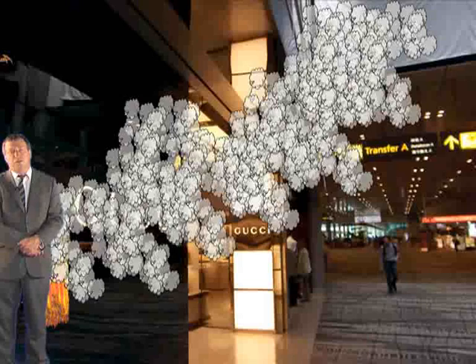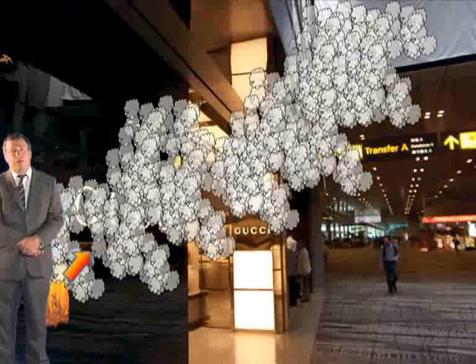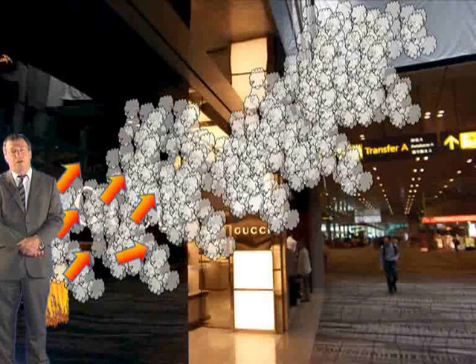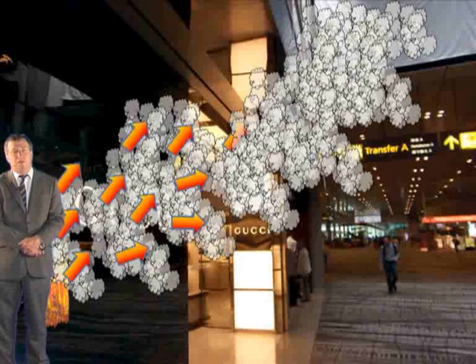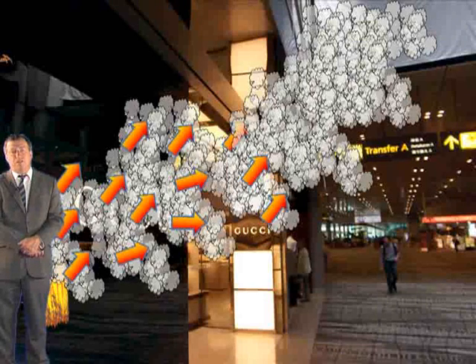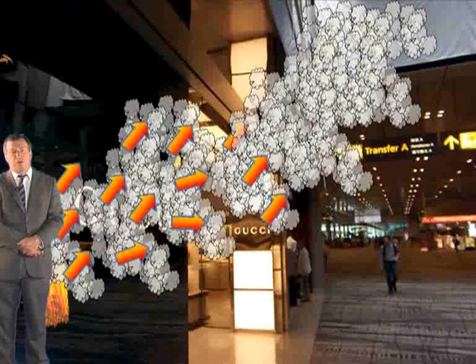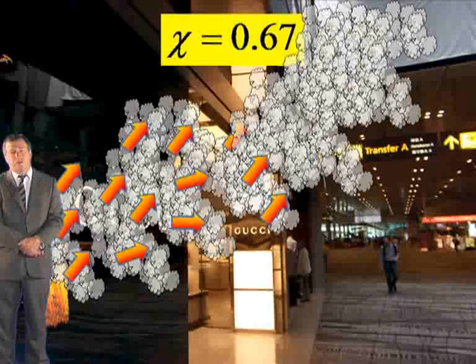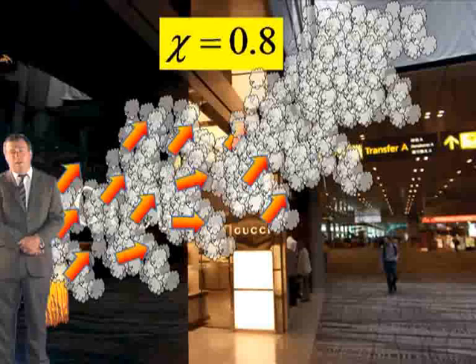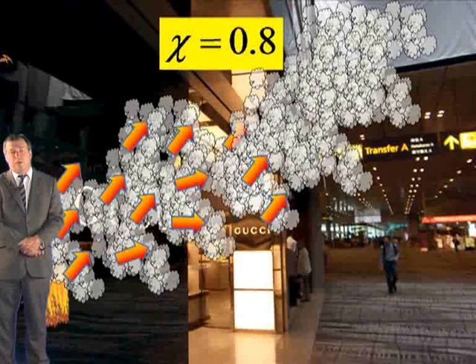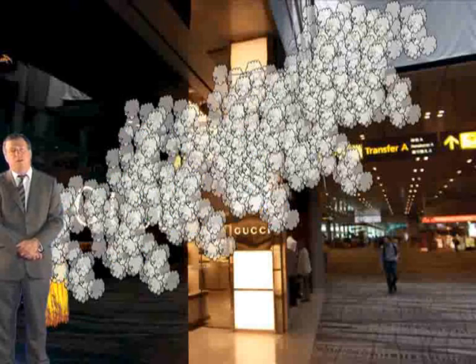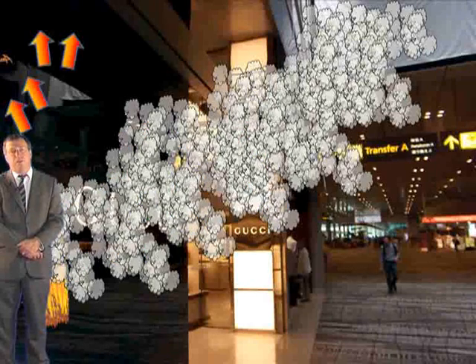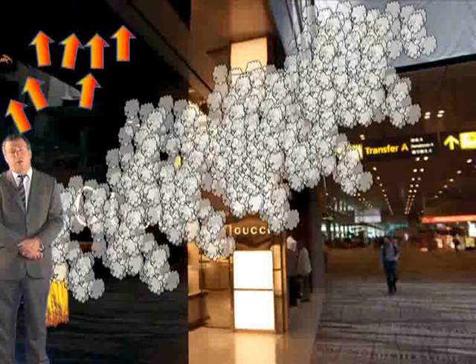BS 7346 Part 4 gives a discussion about the amount of heat that might be carried in the smoke as it leaves the room of fire origin. If you recall, for axisymmetric fires, we assumed a value of chi of between 0.67 and 0.8. This was the fraction of the total heat output that was given out as convective heat. In the complex plume scenario, there is the opportunity for heat to be removed from the smoke as it travels through the building before rising into the atrium.